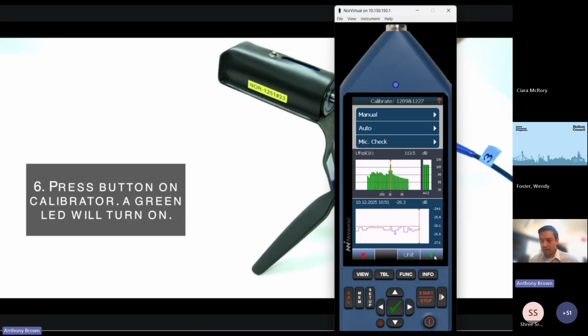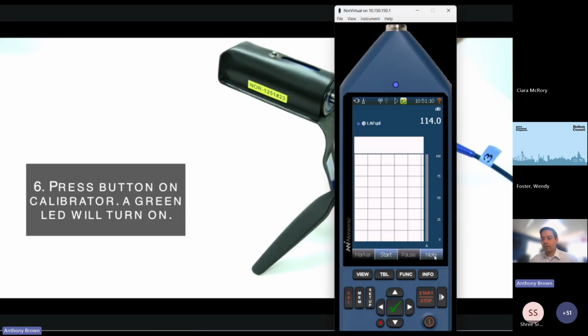So you just press a tick to save it and then tick again to save again. But you should see, I've left the calibrator on the end of the meter. You should see it show 114. So as long as you've got that, you know that your microphone's working. And then I'll just take the calibrator off the end of the microphone. And that's done. So the process is from start to finish.